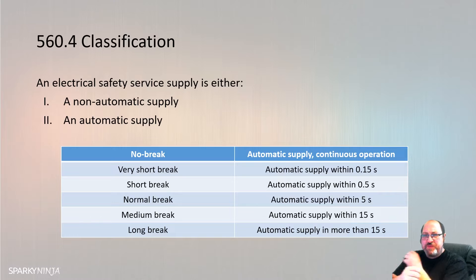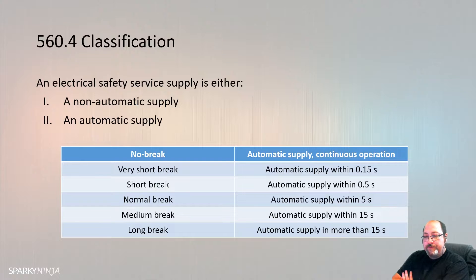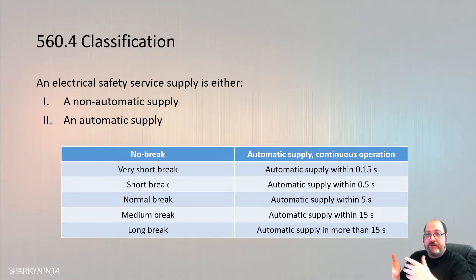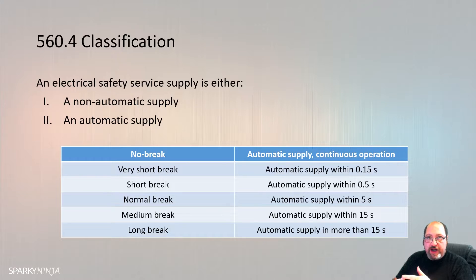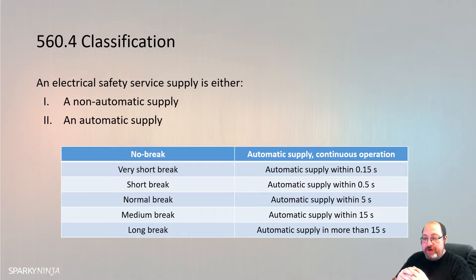I touched on this briefly in the previous video. 560.4.1 states that an electrical safety service will either be a non-automatic supply, which is initiated by an operator, or an automatic supply, where it's independent of an operator. For an automatic supply, the question is how automatic - so there is a changeover time to consider. We have 'no-break', which is an automatic supply producing a continuous supply within specified conditions during the transition period, for example regarding variation of voltage and frequency.